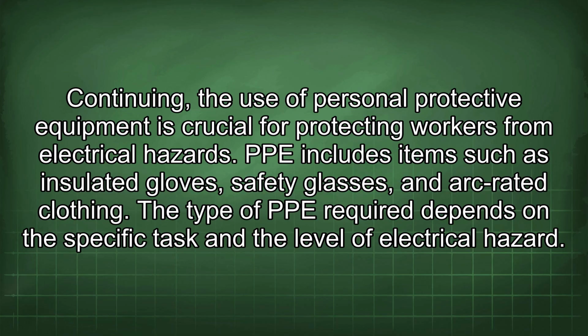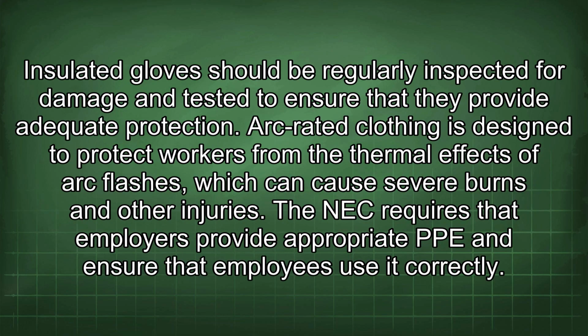Continuing, the use of personal protective equipment is crucial for protecting workers from electrical hazards. PPE includes items such as insulated gloves, safety glasses, and arc-rated clothing. The type of PPE required depends on the specific task and the level of electrical hazard. Insulated gloves should be regularly inspected for damage and tested to ensure that they provide adequate protection. Arc-rated clothing is designed to protect workers from the thermal effects of arc flashes, which can cause severe burns and other injuries. The NEC requires that employers provide appropriate PPE and ensure that employees use it correctly.